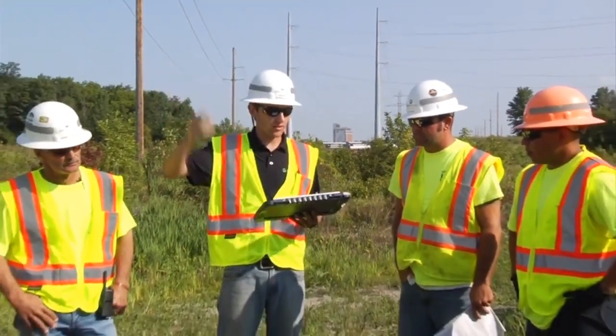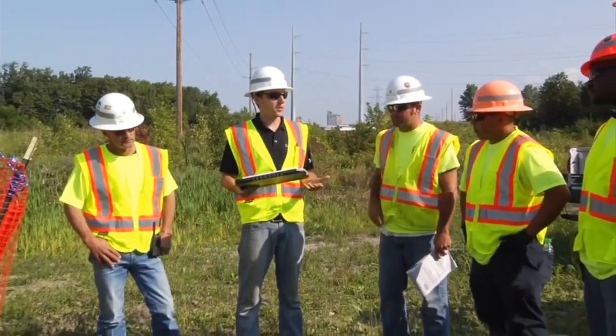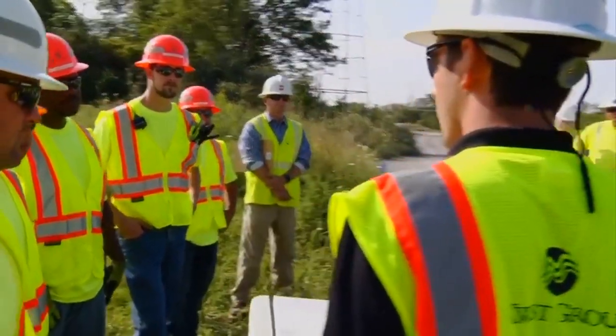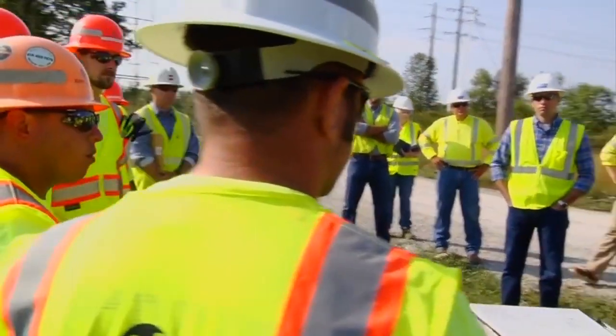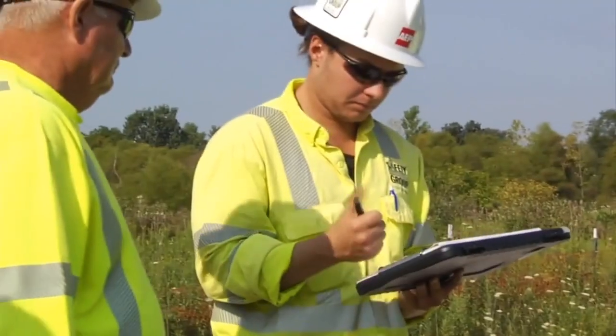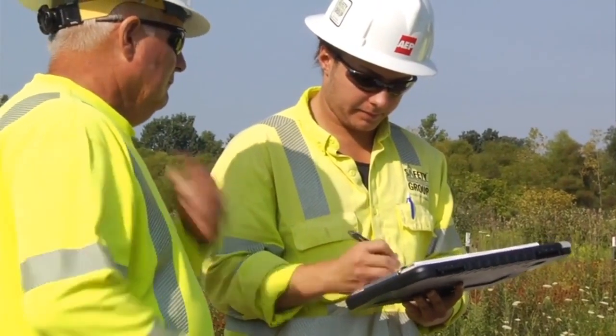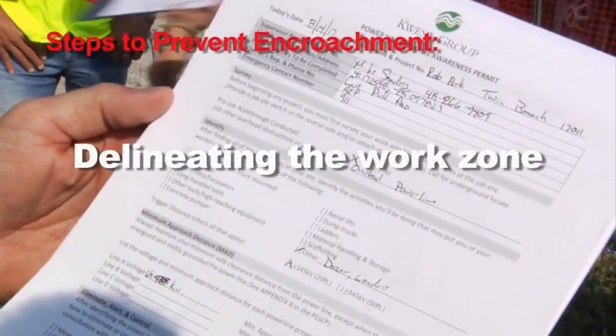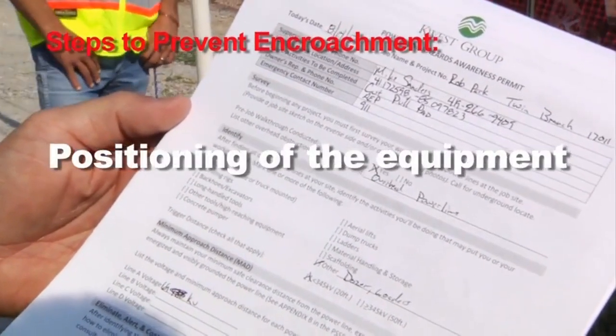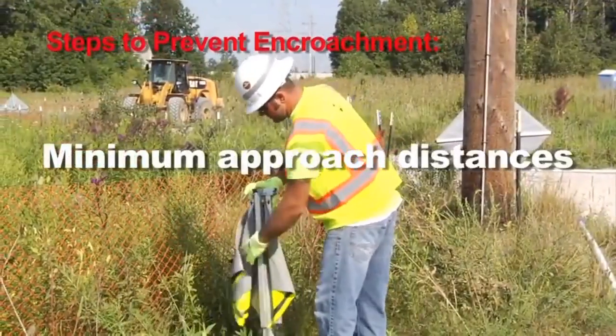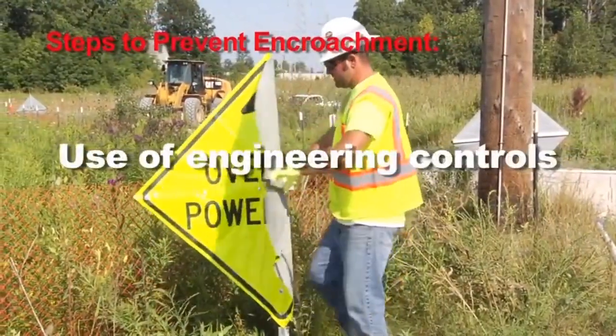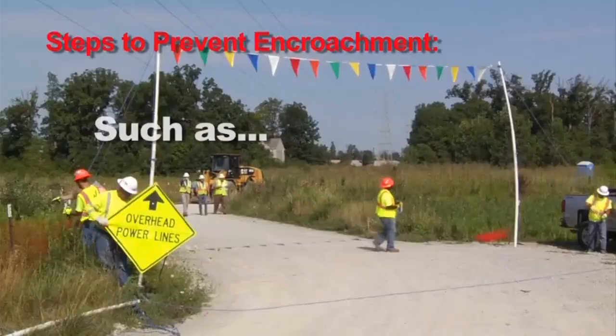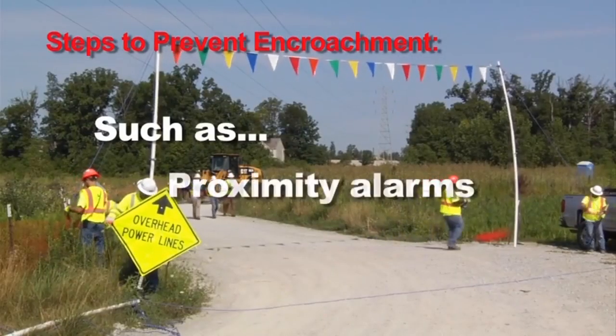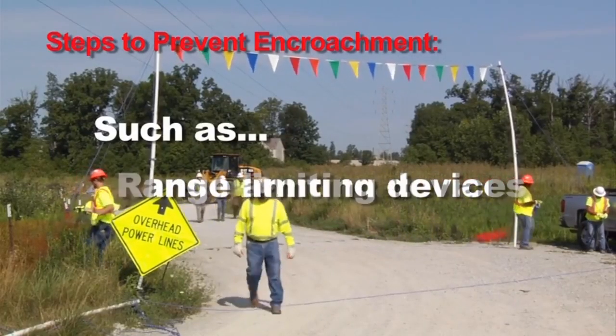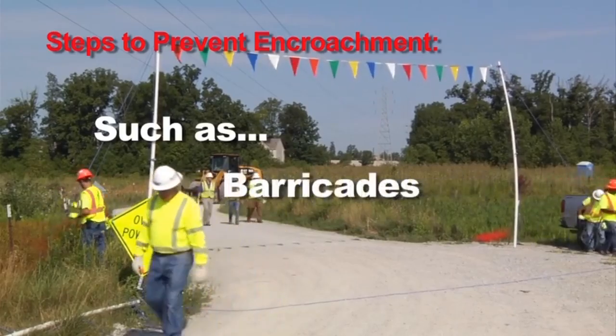If the trigger distance to energized lines or equipment would be encroached, the contractor shall conduct a documented planning meeting with the operator and the other workers who will be in the area of the equipment or load to review the location of the energized lines or equipment. The planning meeting shall address the steps and provisions that will be implemented to prevent encroachment, including delineating the work zone, positioning of the equipment, the voltage with applicable minimum approach distances, and the use of available engineering controls. For example, proximity alarms, range limiting devices, insulating protective material, and barricades.